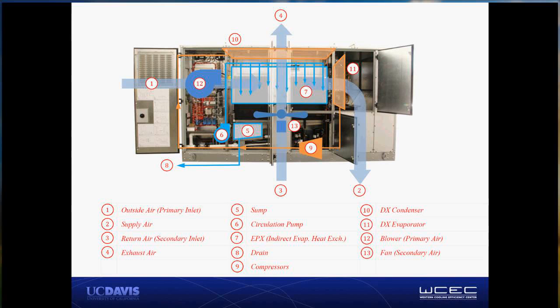When there's a call for, say, second and third stage of cooling from the space because room temperature is rising, the equipment will kick on a vapor compression system. Outlet air from the indirect evaporative passes through a vapor compression evaporator, and it's subsequently cooled. The equipment includes two stages of vapor compression. The equipment is very interestingly designed to use return air from the space as the secondary airstream to drive the indirect evaporative cooling process. This is advantageous because the room conditions are cooler than outside air conditions and typically have a lower humidity ratio. So you get to start from a point that's much better to drive an evaporative process. It already has a much lower wet bulb temperature.